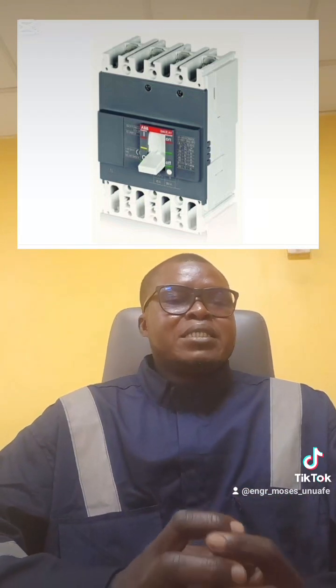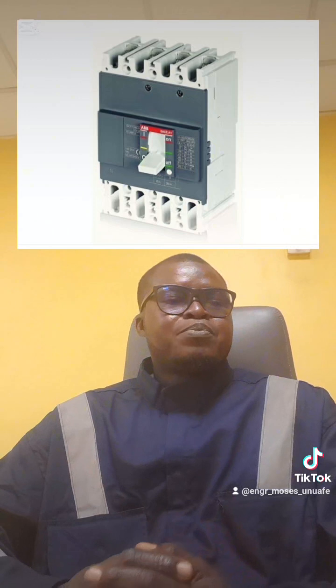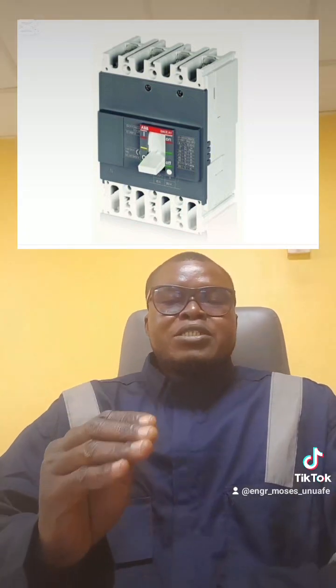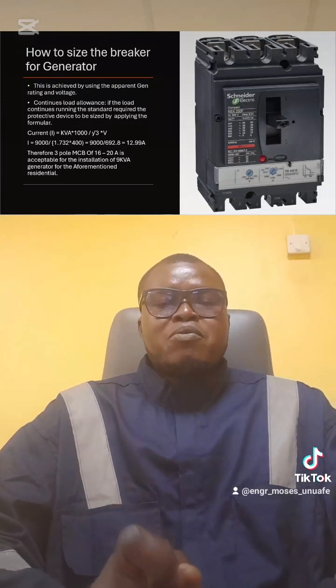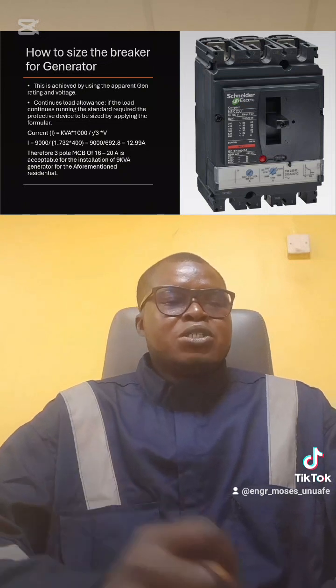To achieve this, using the apparent generator rating and voltage, we know that the generator is going to be a continuous running load. And the standard is that we have to calculate the current using the formula: current equals kVA times 1000 divided by the root of 3 times voltage.